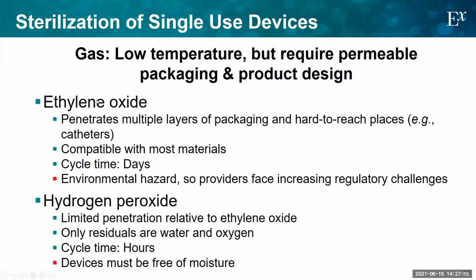So we've probably all heard about ethylene oxide. This is a very potent sterilization agent. It's able to penetrate multiple layers of packaging. It's great for devices like catheters that have lots of nooks and crannies. It's compatible with most materials, has a fairly short cycle time of days, but as you may have heard, it presents an environmental hazard. So they found high rates of cancer around these plants that do the ETO sterilization. And so there's a lot more pressure from the regulatory agencies.